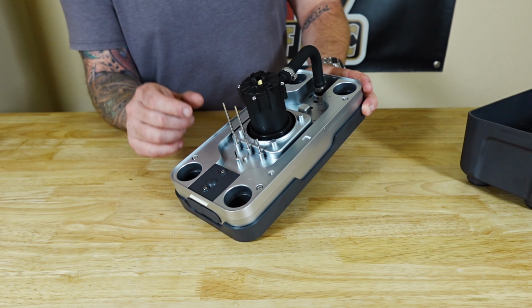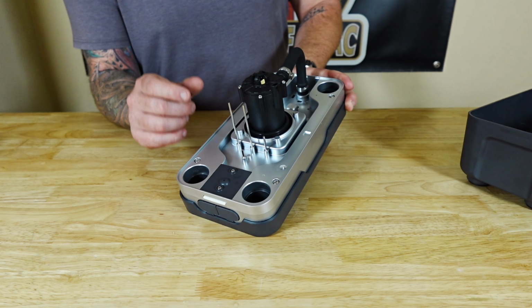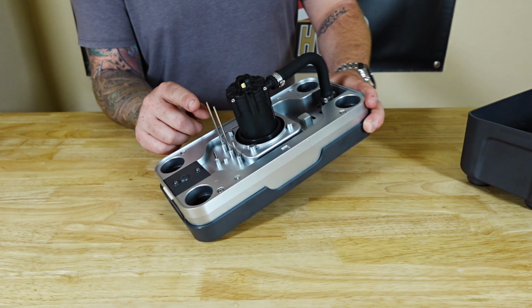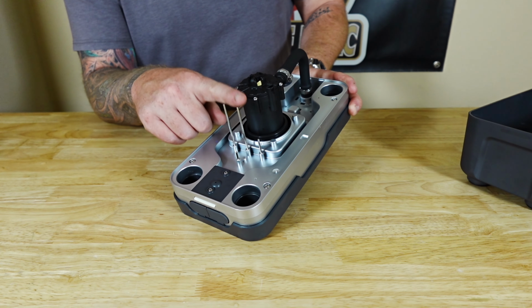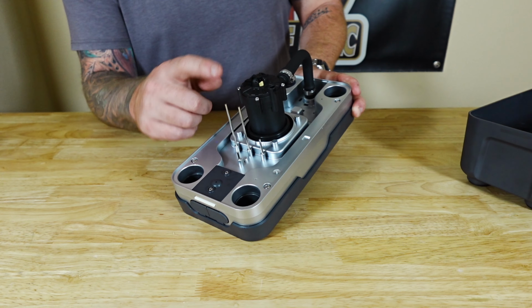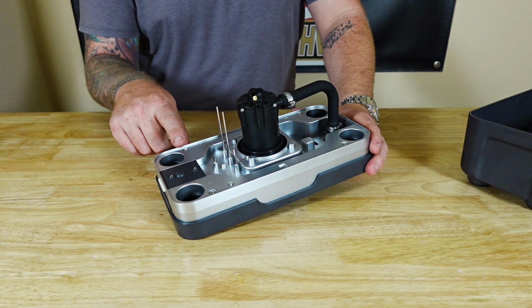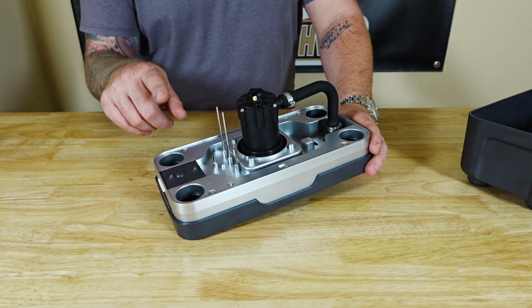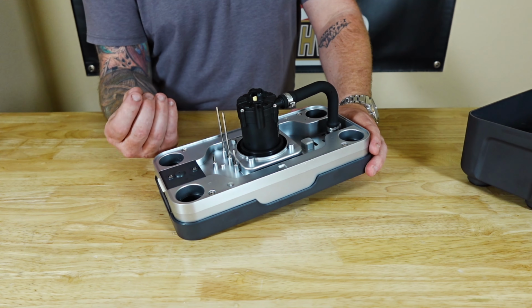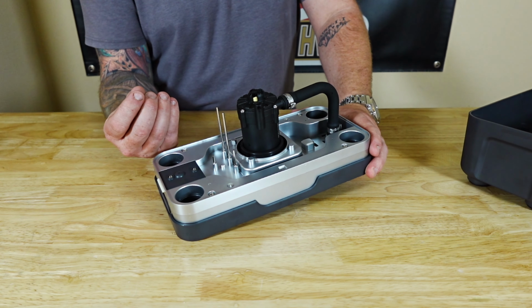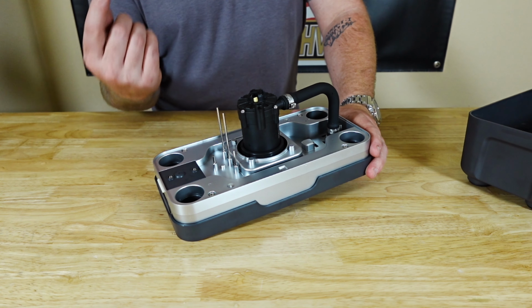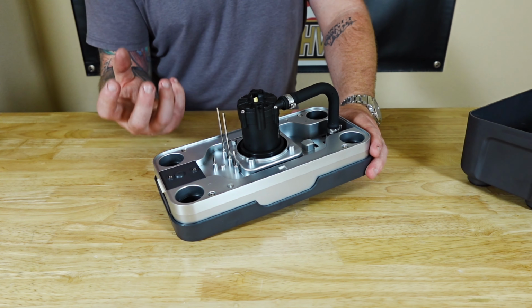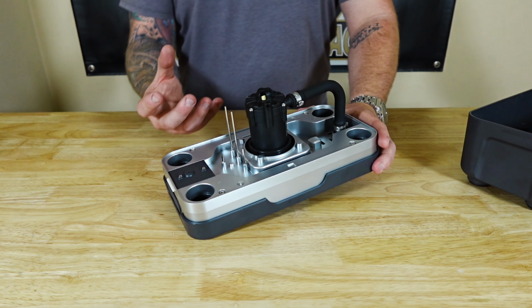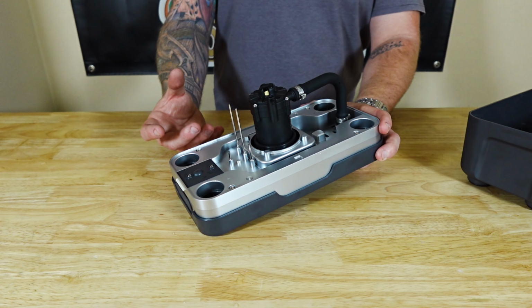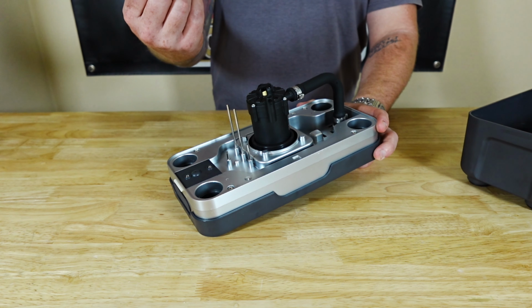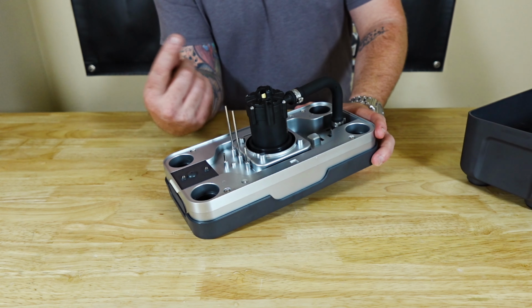You don't see a float switch. You don't see a styrofoam float, meaning this system has a normally open set of contacts with probes to turn the water on. You're not going to have something that floats up and down and can get stuck, because just like an SS1 or SS3, you can have buildup of algae or zoogloea on those float switches, causing those systems to fail since the center rod sticks to the styrofoam.